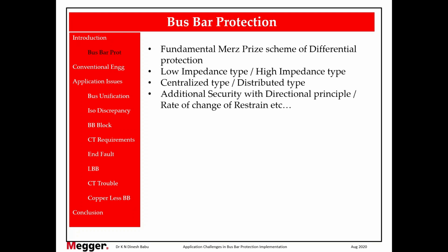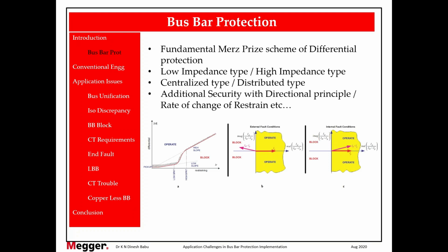Okay, this is an interesting area which we can understand better, because these are the fundamental concepts available in modern technology inside numerical relays, like directional principle, rate of change of restraint algorithm. So what are these actually? To better understand, I can show it like this. When we are configuring a slope, let us say slope 1 and slope 2 in differential testing, we can say 18% as slope 1, 20% as slope 2. Or 20% as slope 1, or in slope 2 somebody says 80%, somebody says 81%.